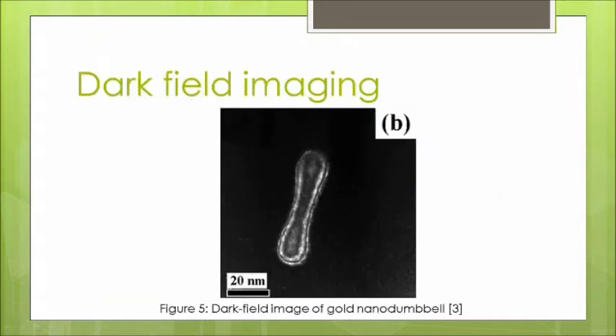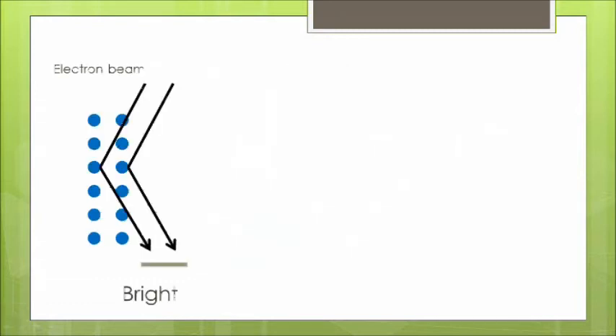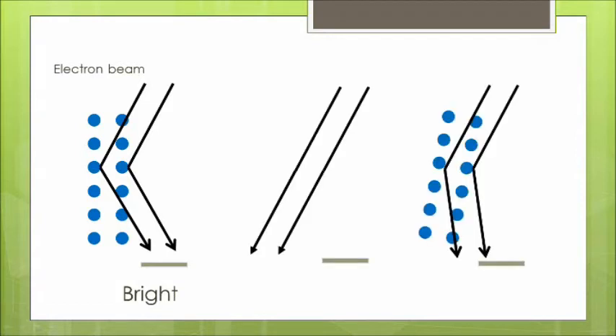A dark field imaging uses a phenomenon known as Bragg scattering. The conditions for an incident wave to be reflected happens at a specific angle. To observe this image, we have to block out the central electron beam and position the electron beam at that specific incident angle. The scattered beam that comes back at us represents the area where there is matter, and the intensity depends on the incident angle. The remaining area where Bragg scattering conditions are not met remains dark.